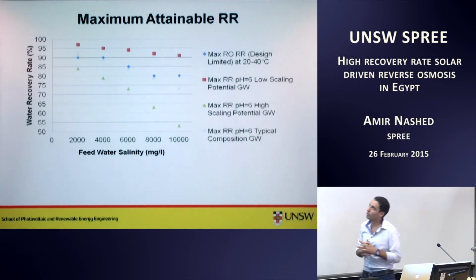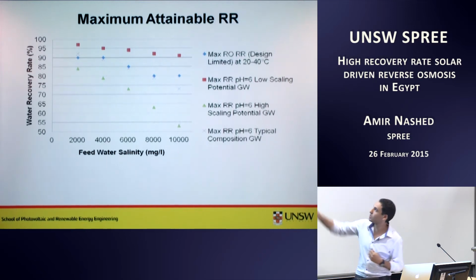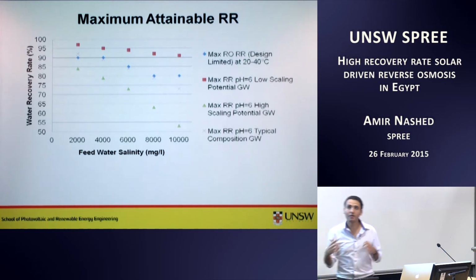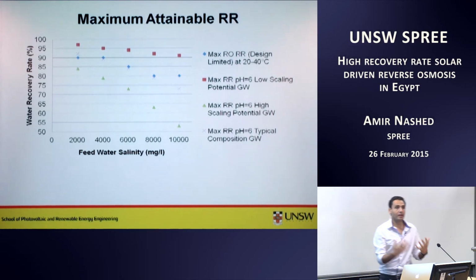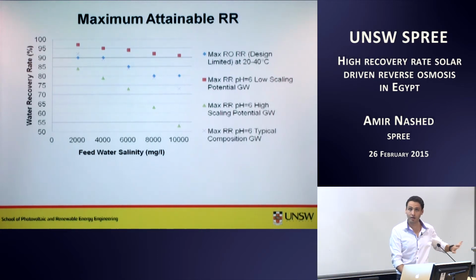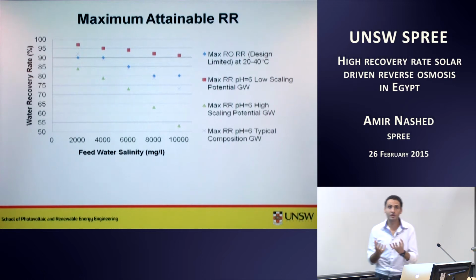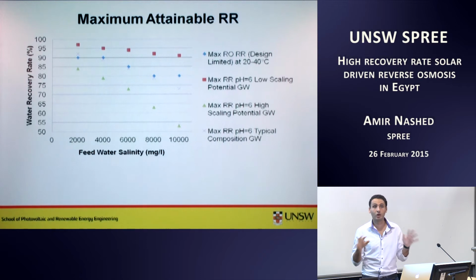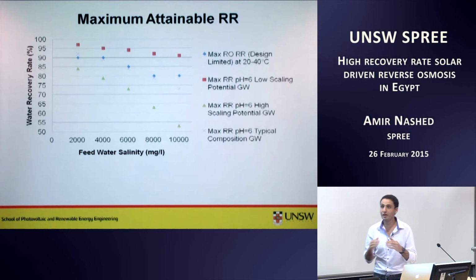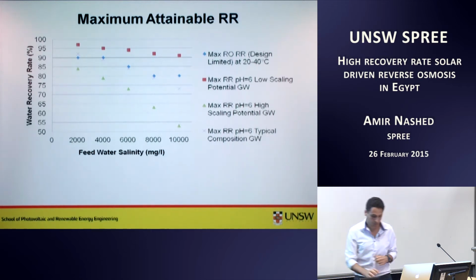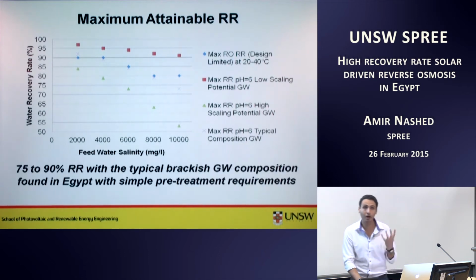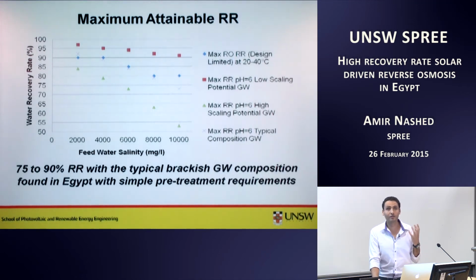But what is more interesting is that the reverse osmosis plant itself has its own recovery rate limitations, which is the blue dots. This means that if you try to attain a higher recovery rate, assuming there is no scaling limitation, the modules themselves cannot support this recovery rate, and they will start to operate outside the window recommended by the manufacturer. So you have a limitation by the RO plant itself. What I found out is that for the typical groundwater composition in Egypt, you can get from 75 to 90% recovery rates, which is pretty good.